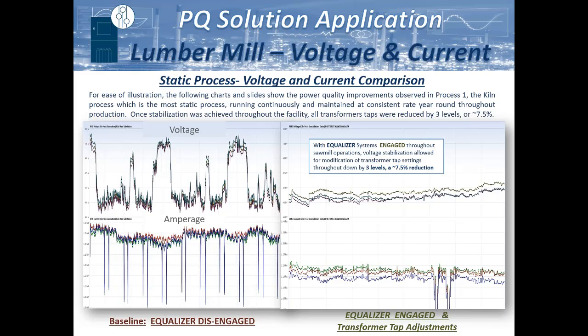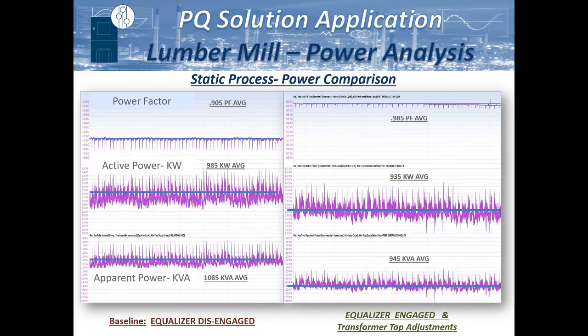You can see after the fact, now after implementation of the equalizer systems throughout the facility, we were able to adjust all of the transformers throughout the facility by 3 levels, reducing their secondary supply level by about 7.5%, and then maintaining that. So in looking at some of the power profiles, on this static process, they were already running at a 0.90 power factor. So now we've actually increased this. This was actually our ActiveR system, so that has a little bit slower of a response time and is designed for very steady state processes, which this is obviously applicable to.